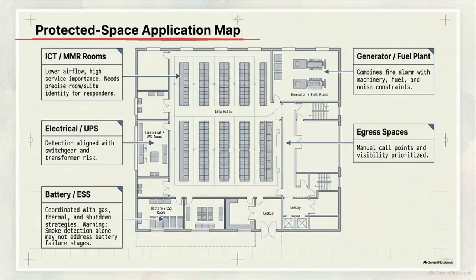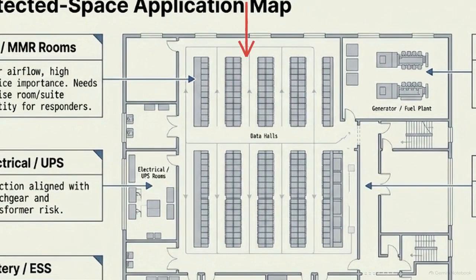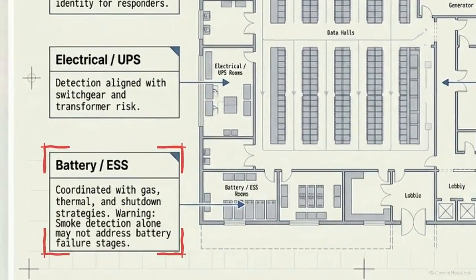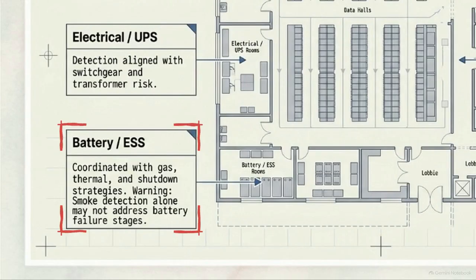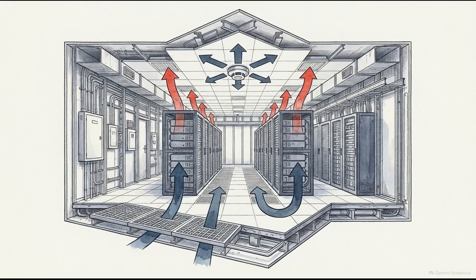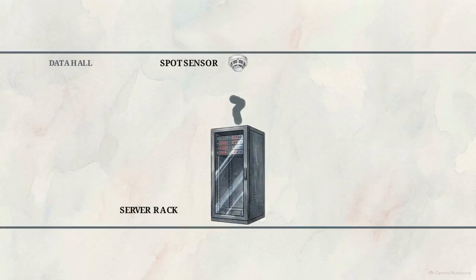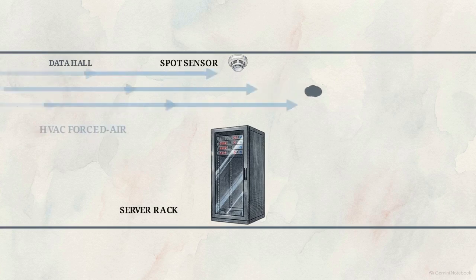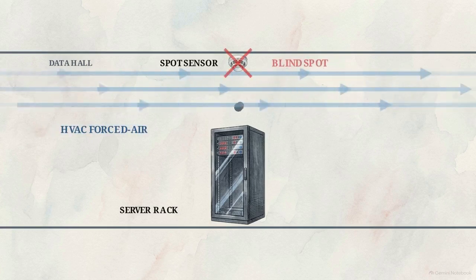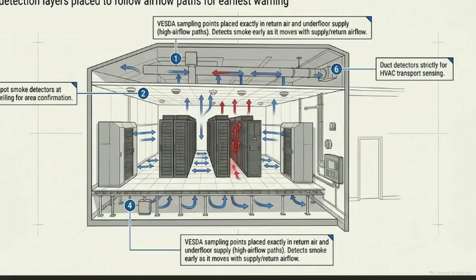This protected space application map shows how the threat profile changes across functions. In central data halls, high-velocity airflow is the primary obstacle. But in battery and ESS rooms, the threat shifts to gas emissions and thermal runaway, requiring coordination with shutdown strategies. A defensible architecture maps detection technology directly to the physics, fuels, and airflow of each isolated zone. Traditional ceiling-mounted detectors often fail in data halls because massive HVAC forced air currents blow incipient smoke straight past the sensors. Effective detection follows the physical movement of the air.